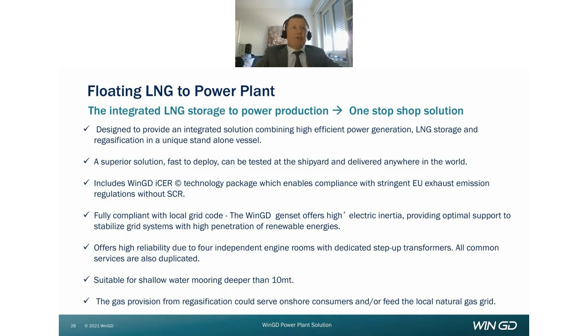It's highly reliable due to 4 independent engine rooms with dedicated step-up transformers. All common services are also duplicated to avoid single-point failure. Gas provision from regasification could serve the onshore consumer and feed the local gas grid if needed. Liquid backup fuel provision is also foreseen in case of gas supply shortage. It's suitable to be deployed in shallow water, mooring deeper than 10 meters.